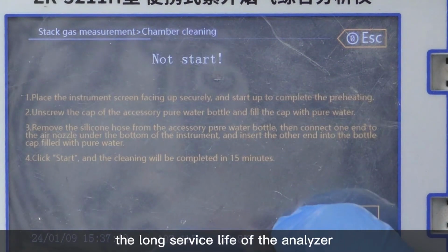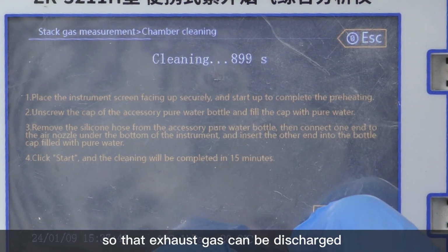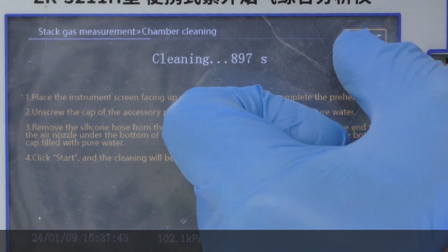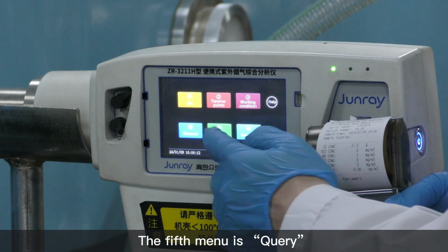Let's do chamber cleaning after measurement. This step is necessary to ensure the long service life of the analyzer. Be sure put the analyzer into the ambient air. And click Start. This process will clean the entire air path so that exhaust gas can be discharged from the exhaust pipe. The 5th menu is Query.